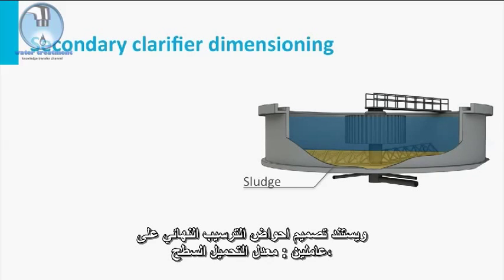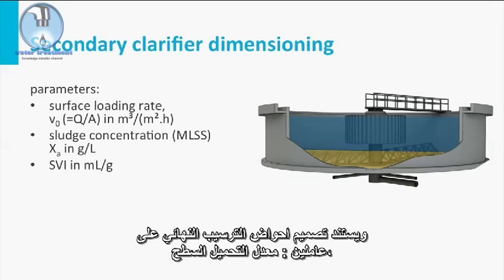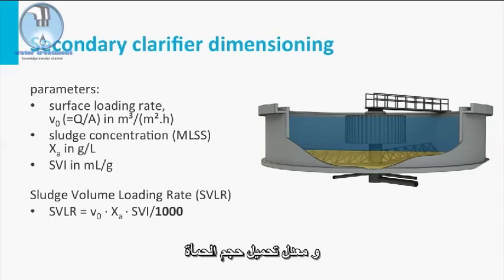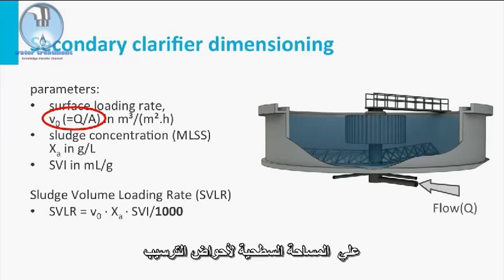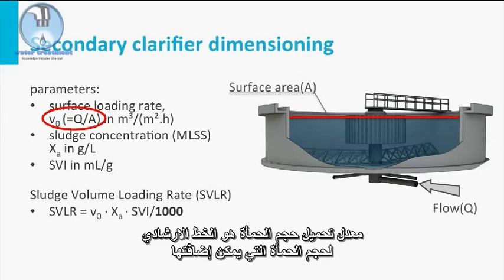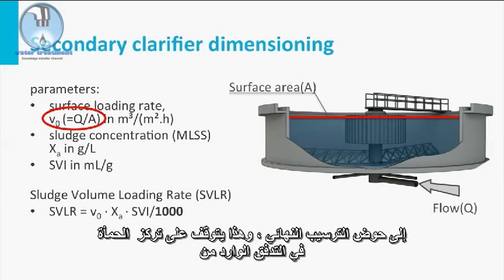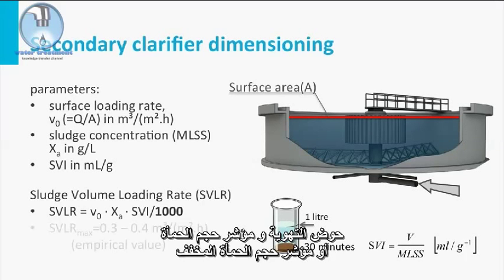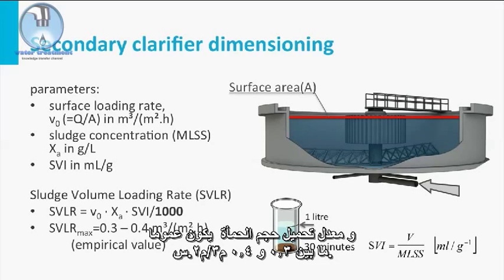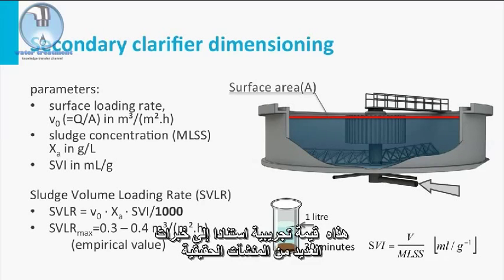The final clarifier design is based on two parameters. The surface loading rate is the simplest, as it is nothing more than the flow divided by the surface area of the clarifier tanks. The sludge volume loading rate is a guideline for the volume of sludge that can be added to a final clarifier, depending on the sludge concentration in the flow from the aeration tank and the sludge volume index or diluted sludge volume index. The sludge volume loading rate generally lies between 0.3 and 0.4 cubic meters per square meter per hour. This is an empirical value, based on experiences of many full-scale installations.